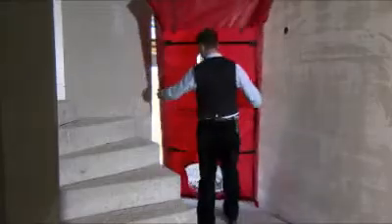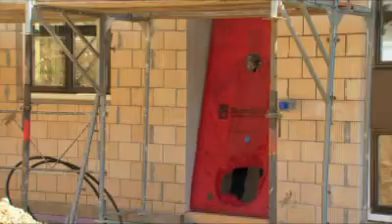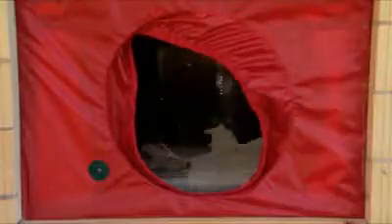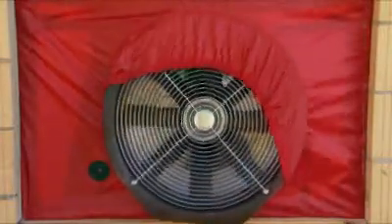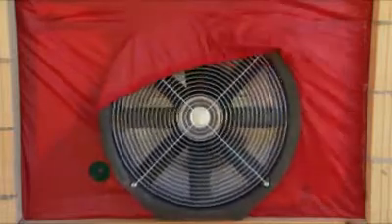For the measurement, a frame covered with an airtight membrane is fitted into the front door frame. All other openings of the building are closed. The main component of a blower door test set-up is a powerful fan. The fan is installed in the opening of the membrane.